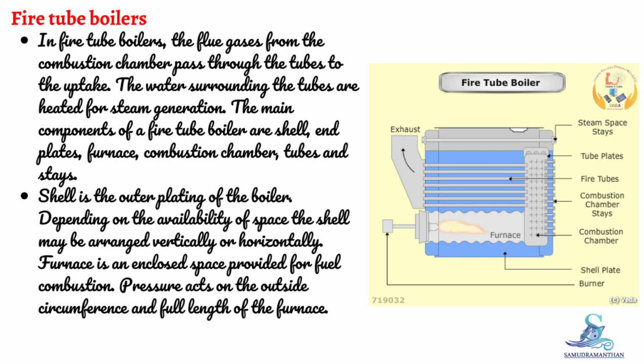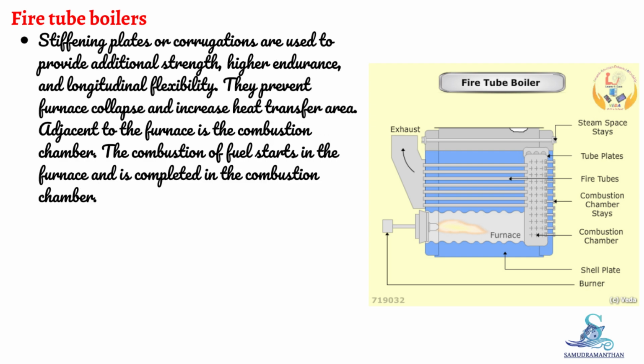Furnace is an enclosed space provided for fuel combustion. Pressure acts on the outside circumference and full length of the furnace. Stiffening plates or corrugations are used to provide additional strength, higher endurance, and longitudinal flexibility. They prevent furnace collapse and increase heat transfer area.